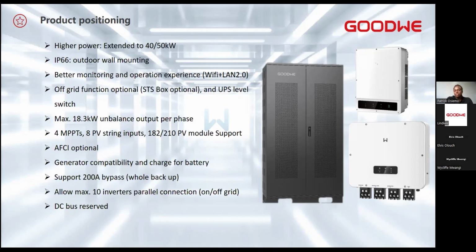The 40 and 50 hybrid inverter has a UPS level switching time of less than 10 milliseconds. And we have a 100% unbalanced output, so loads of up to 18.3 kilowatt. You can supply power according to the demand per phase, not just limiting or uniformizing the generation of the inverter. So if you want to increase your self-consumption or PV utilization, it's just a button configuration, and you activate the 100% unbalanced output. By that step, each phase will be supplied according to the demand or the load per phase independently.